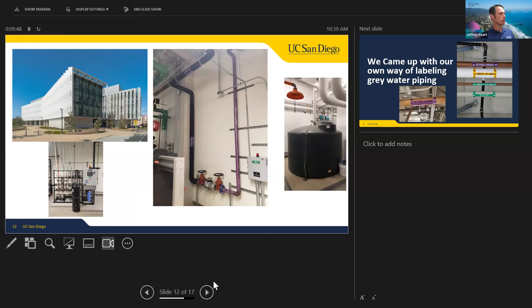So we came up with our own labeling for the piping inside these gray water systems: label the piping with what the source water is, using a purple label with white lettering, very standard, but labeled for the source, and then labeled again post-treatment. So you'd have a label like recovered condensate or RO discharge, and after it goes through treatment, something like condensate water. This comes from my perspective in health and safety, so that facilities staff up in those buildings know where the hazard is. RO discharge is pretty much just salty, but the condensate water could have bacteria in it, it could have Legionella.